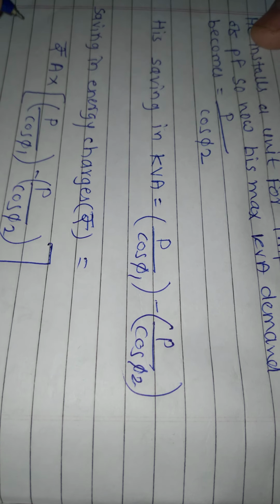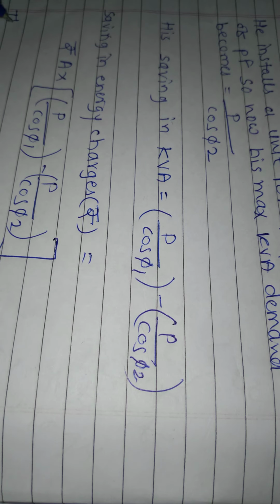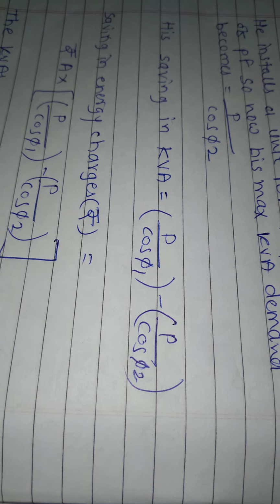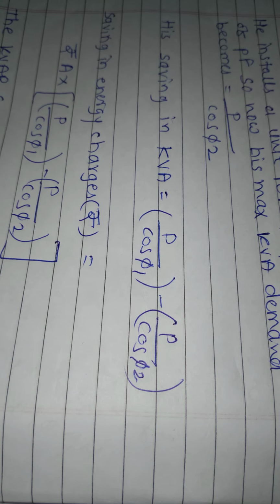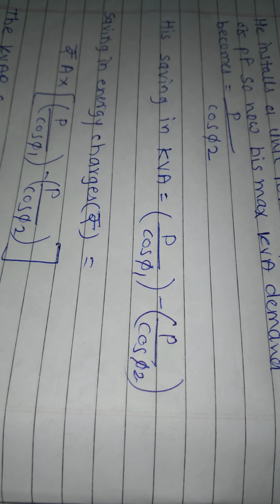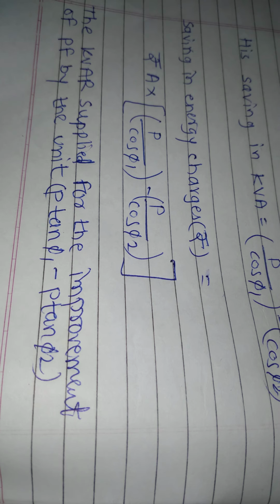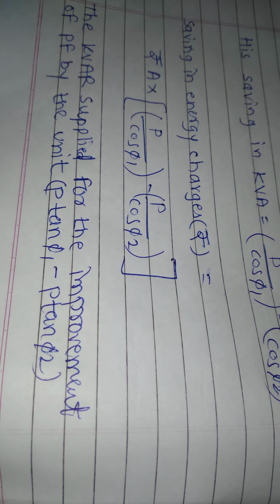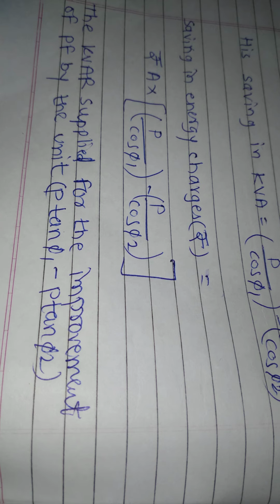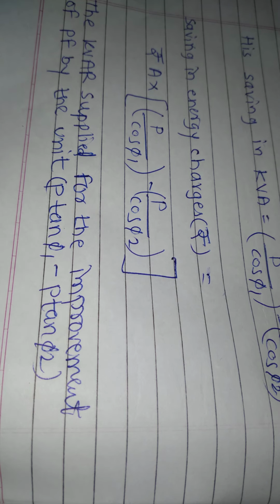The kVAR supplied for the improvement of power factor by the unit is P tan phi 1 minus P tan phi 2.